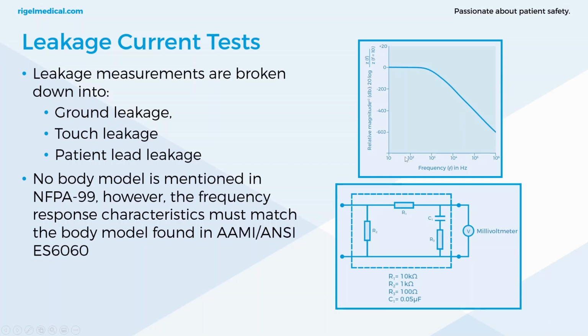So the circuit is not mentioned in NFPA 99. There's no circuit like this really specified. This is from IEC 60601, and it does state that it should be close to the one found in that standard. And that just ensures that you've got the same frequency characteristics. So if you've got this circuit, then you'll be matching the frequency in the 60601. Now NFPA 99 does state that the frequency should closely match that of the one found in 60601. Now to measure these currents, you just need a meter which has the same frequency response characteristics of this body model.